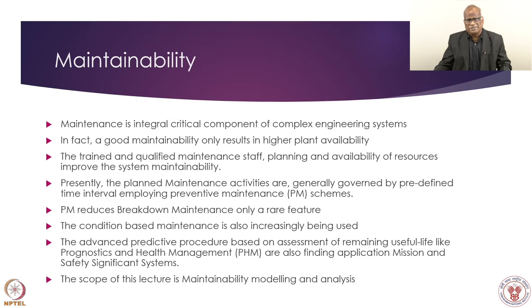Slowly we are also embracing condition-based maintenance because technology has advanced. We can put sensors on the equipment — whether a temperature sensor, humidity sensor, or level sensor — and know the condition of the equipment: whether sufficient oil is there, temperature is not going beyond limits, or any vibration, which is a very significant indicator. These attributes are monitored online so that prior action can be taken before degradation takes the component to a failed state.